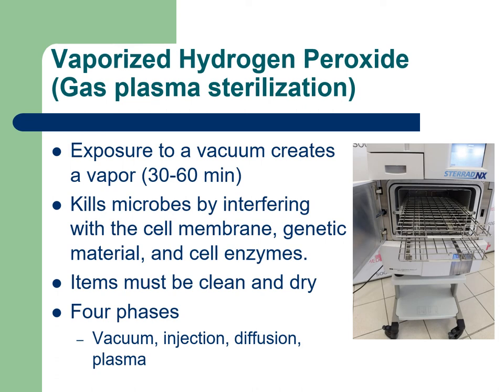There are four phases for gas plasma sterilization. The first is the vacuum phase, which takes out all the air, sounding similar to the conditioning phase of the steam sterilizer. Then there's the injection phase, where the hydrogen peroxide is injected into the chamber, similar to the exposure phase of the steam sterilizer.